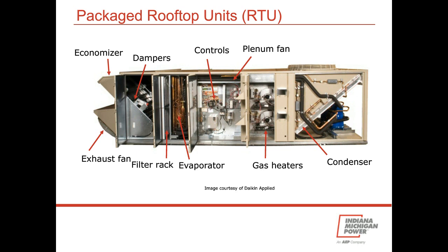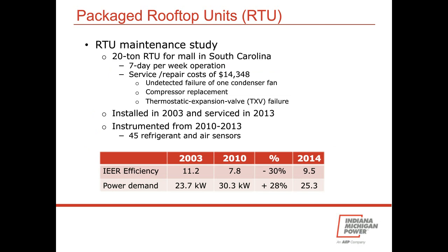And what impact does good maintenance have on rooftop performance? I'm glad you asked. There's an interesting longitudinal study of rooftop units not too long ago, conducted by Advantech Consulting, Michael West, and Richard Combs. They came across a mall constructed in 2003 in South Carolina that had 11 rooftop units, totaling just over 200 tons. The area served by one particular rooftop unit was a large open retail space that had high ceilings, subject to frequent door openings, which in and of itself provided some uncontrolled but pretty effective fresh air ventilation.